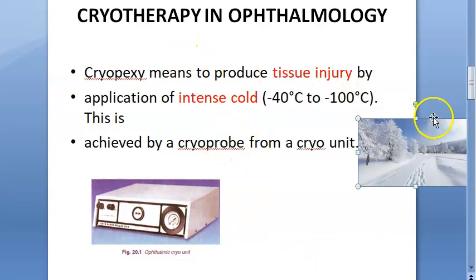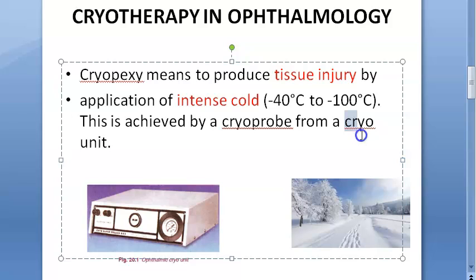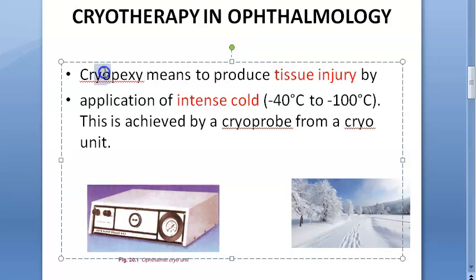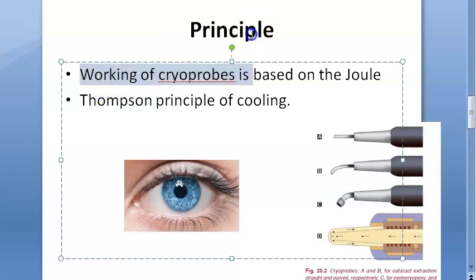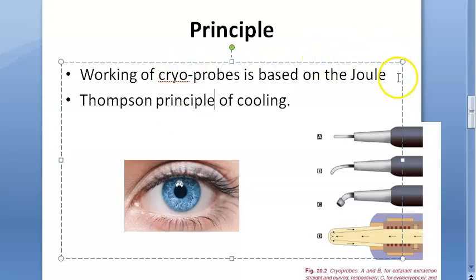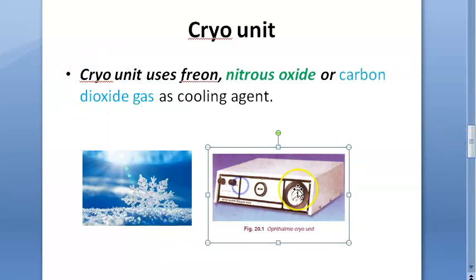To achieve cryotherapy you need two things: cryo probes and a cryo unit. This is the ophthalmic cryo unit. Cryopexy means to produce tissue injury using intense cold, which is achieved by a cryo probe from a cryo unit. The working of cryo probes is based on the Joule-Thomson principle of cooling.